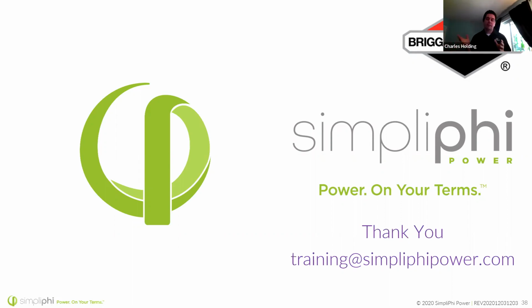A wire sizing question came in, asking if we should be sizing for surge. For example, the battery has that 100 amp surge, or maximum continuous discharge rate. That's a great question. In terms of the ampacity of wires and wire sizing, we helped somebody do this the other day. When you're sizing your equipment, oftentimes the battery bank is capable of surging to more power than the equipment can handle. So if you have a piece of equipment that is only going to be able to output a maximum of 6,000 watts, you can size your wires based on the max load that your inverter can handle, or the max draw out of the batteries.